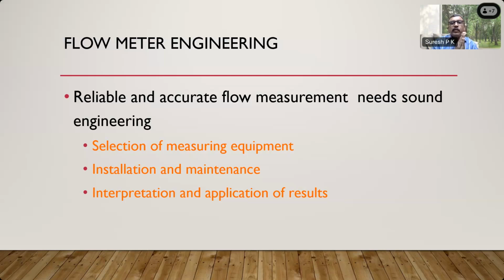Then installation and maintenance. See, it is not like Hero Honda, where you put a meter and then forget it. It's not like that. You have to maintain it properly, install it properly, and give proper flow to it. In between, intermittent checks are required to ensure that the flow meter is performing properly. So installation of the meter is important, maintenance of the meter is important, properly selecting a flow meter is important, and properly placing it at the right place is important. All these things are important. You cannot just say that if I buy a flow meter, I make the flow measurement accurately. That statement itself is totally wrong.